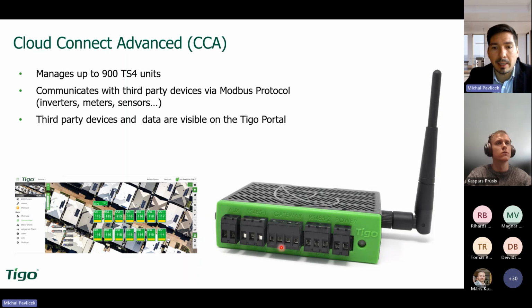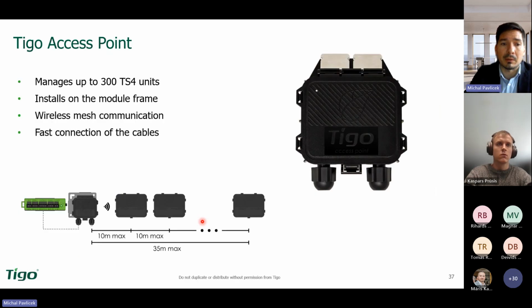The data logger CCA has the connection gateway for the TAPs. You can connect up to 7 TAPs here. It has also the power supply. It has the AUX for controlling the rapid shutdown control for the service purpose. And you can connect also the monitoring of inverter and the monitoring of meteo station if it's in the database. If it's not in the database, you can ask us to add it. Unfortunately, it takes some time, but it's possible to also add new devices to monitor.